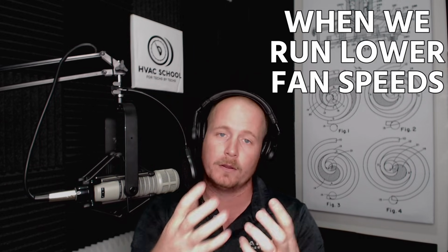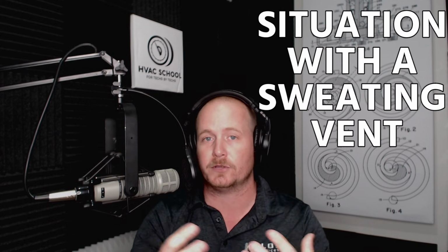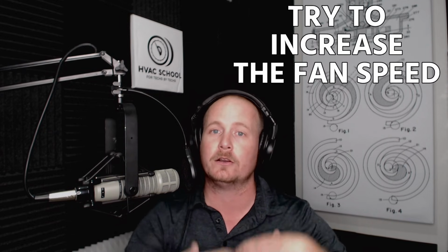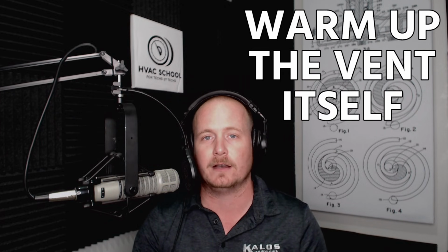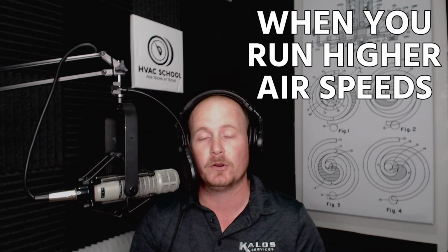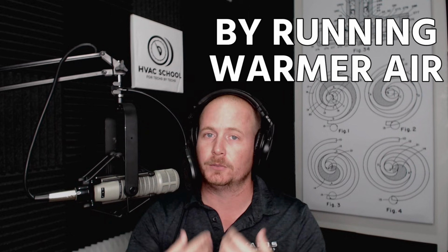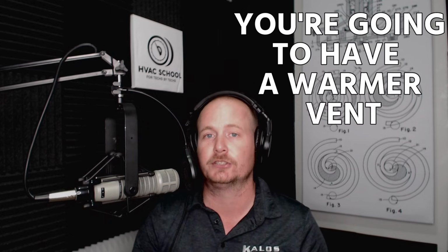So in other words, we're going to remove more latent heat by the equipment when we run lower fan speeds. But in a lot of cases, technicians are going to go to a situation with a sweating vent, and they're going to try to increase the fan speed. And why are they going to do that? They're going to do that because they want to warm up the vent itself. When you run higher air speeds, you have higher air velocities. Higher air velocities means that you're going to have warmer air. And so by running warmer air, it stands to reason that you're going to have a warmer vent.